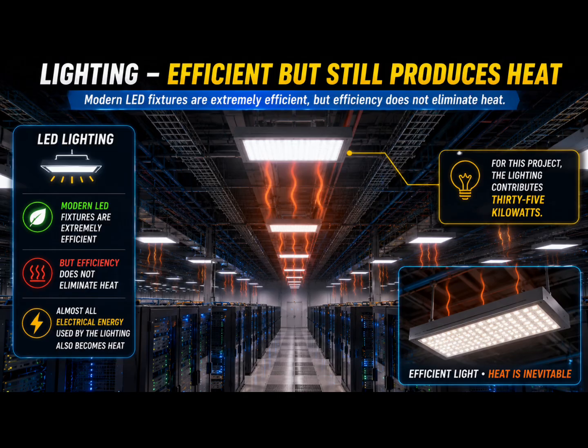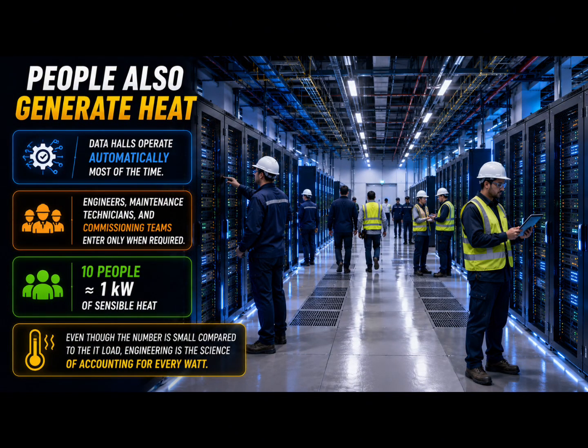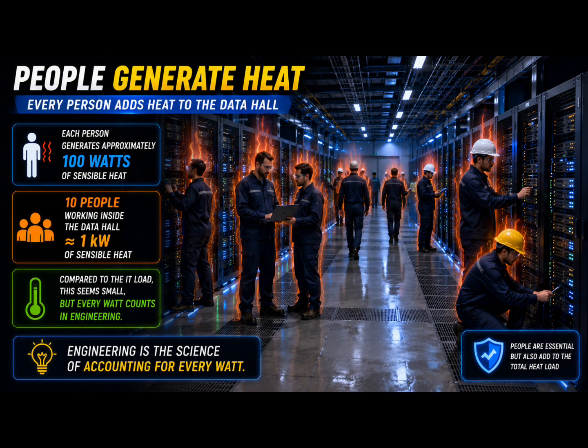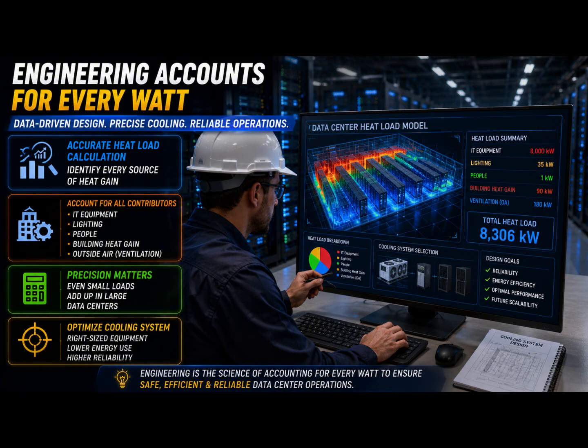Now, let's include the people. A data hall is not continuously occupied. Most of the time, it operates automatically. But engineers, maintenance technicians, and commissioning teams still enter the room. Let's assume 10 people are working inside. Each person generates approximately 100 watts of sensible heat. Together, they contribute 1 kilowatt. Compared to the IT load, that number seems tiny. But engineering is the science of accounting for every watt.